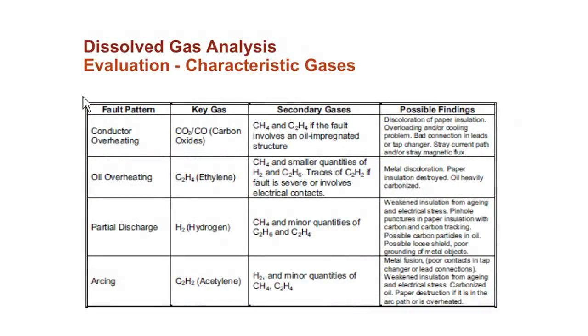Okay, so then we also look at the hydrocarbon gases and then the load profile. The condition of the cooling equipment is very important, especially for coolers. Generally, coolers, meaning where you have a cooler package instead of a fan radiator package, can degrade over time, so it's very important what the condition of those is. And then look for hot spots in metallic materials, so for the core or the current carrying contacts. This you can determine from the DGA. If you do a design review, you can also see if there is this issue there.